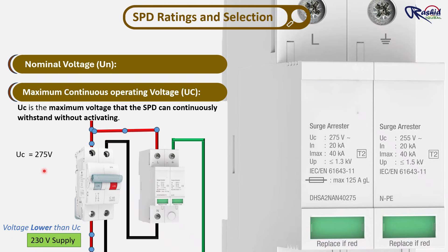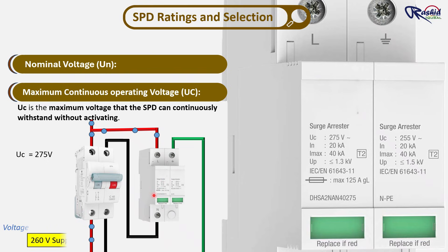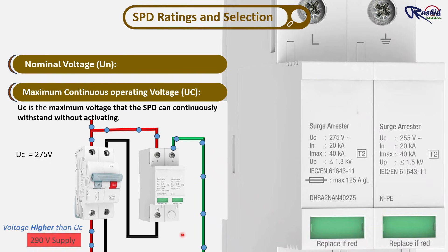For example, with a 230V system, the SPD's UC rating might be 275V. At 230V the SPD stays inactive, and even if a quick spike takes the voltage to 260V, it still does nothing because this is below the UC limit. But when a sudden surge jumps to 290V — higher than the UC rating — the SPD instantly activates and diverts the extra energy safely to earth. Remember, SPD only works for extremely fast spikes or surges lasting microseconds or nanoseconds, like lightning strikes or switching surges. It does not protect against slow or continuous overvoltage.